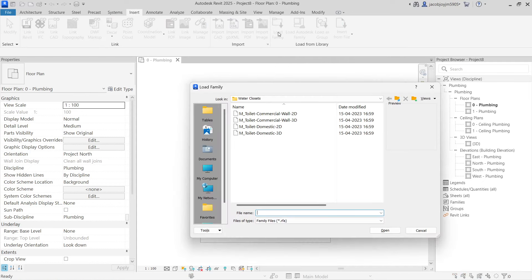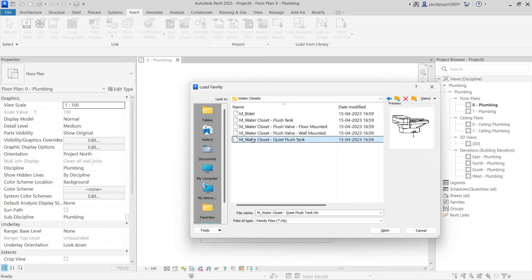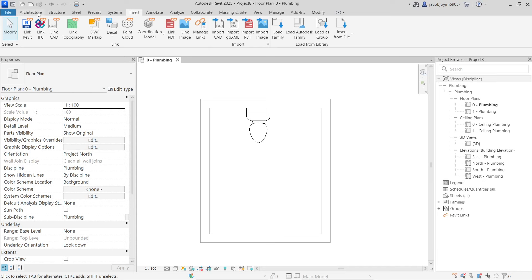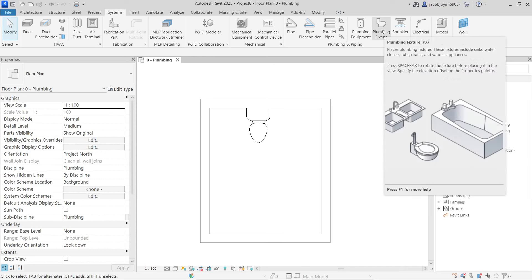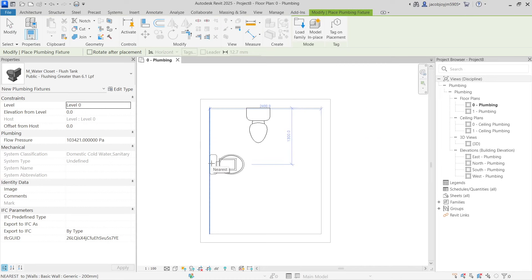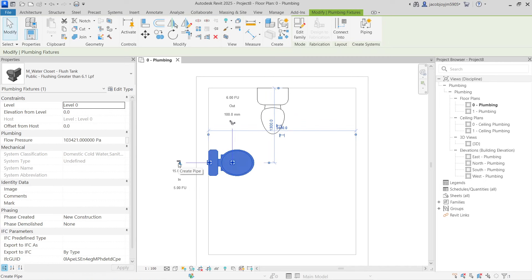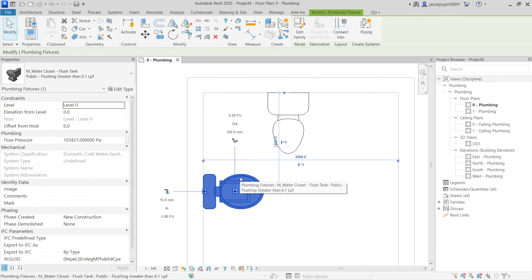Go to Insert > Load Family, then go to the Plumbing folder, select MEP fixtures, and open the same water closet family. Now go to Systems > Plumbing Fixture and place it. When you select it, you can see there is an option to create a pipe — one for outlet and one for inlet. This is the key difference between the architecture plumbing fixture and the MEP plumbing fixture.